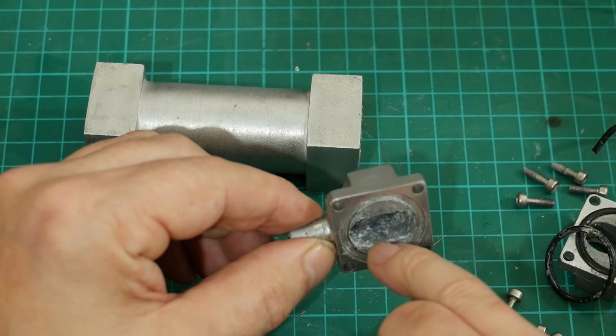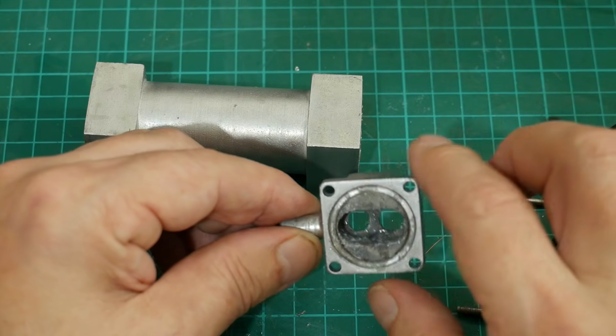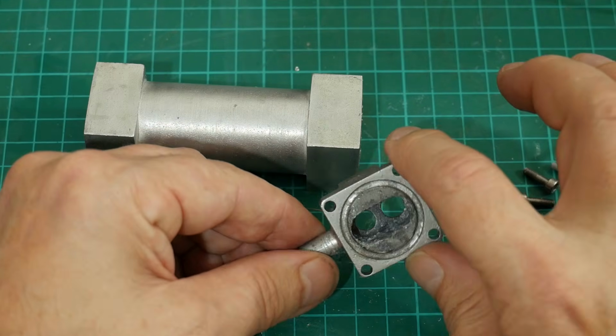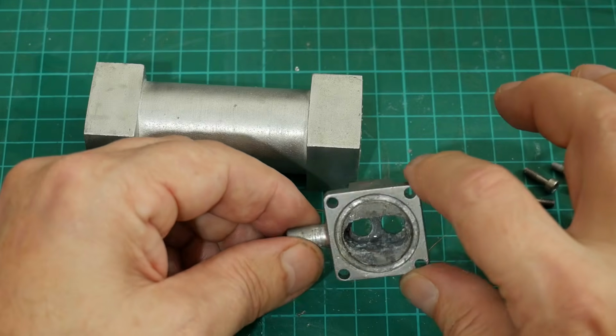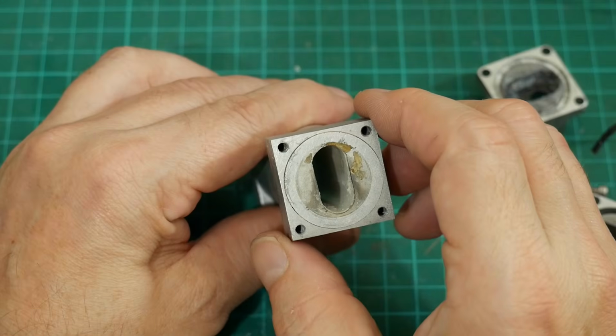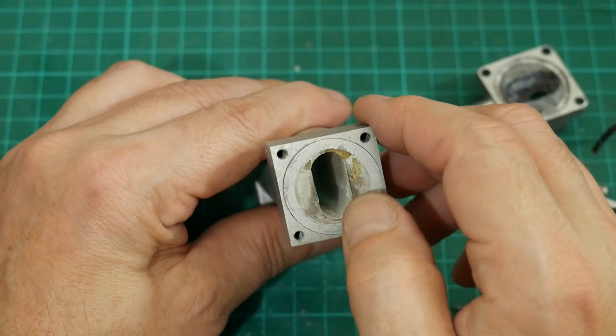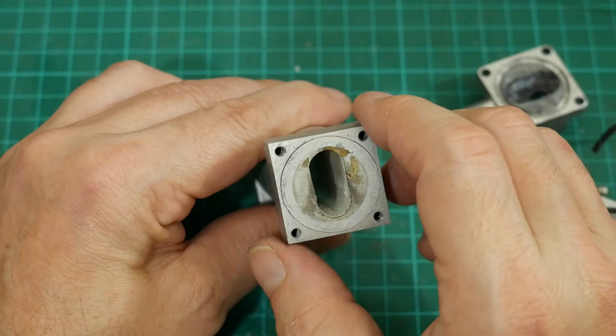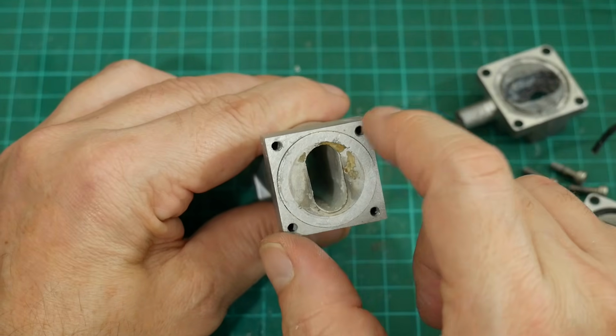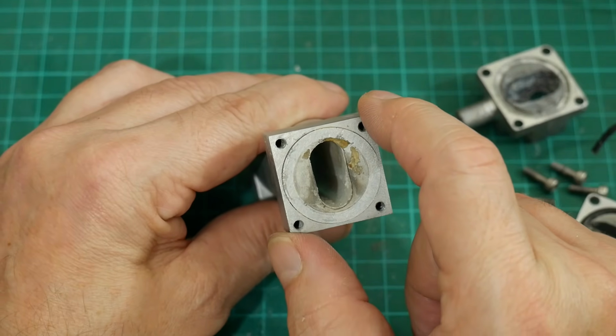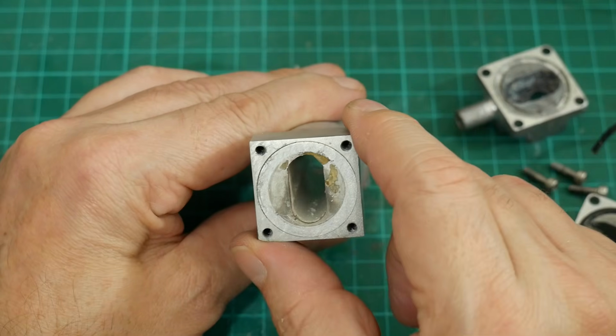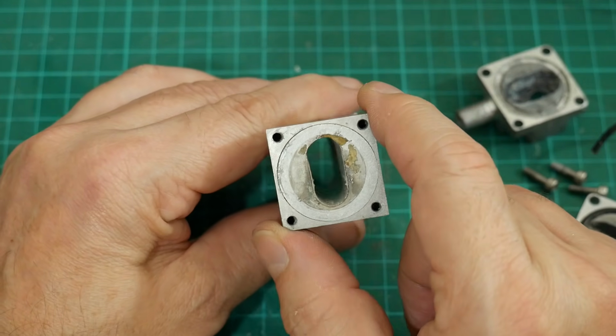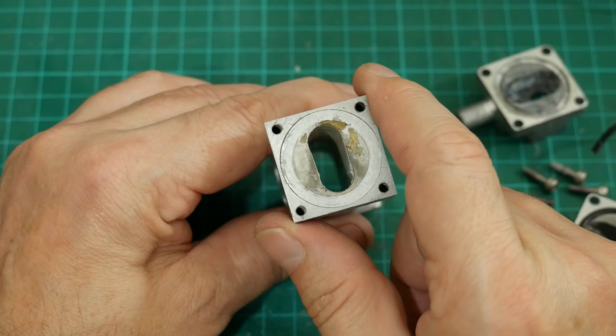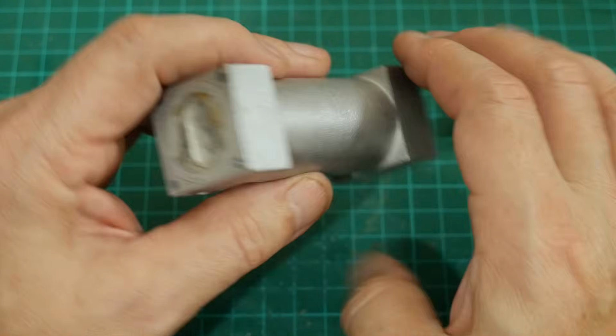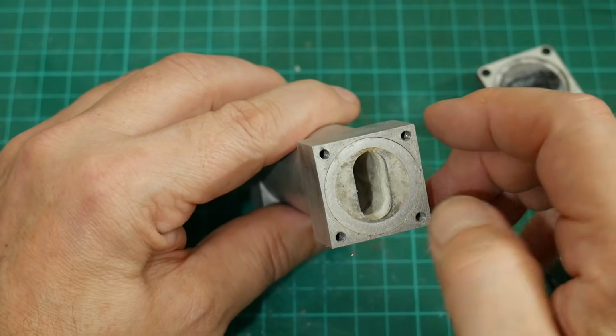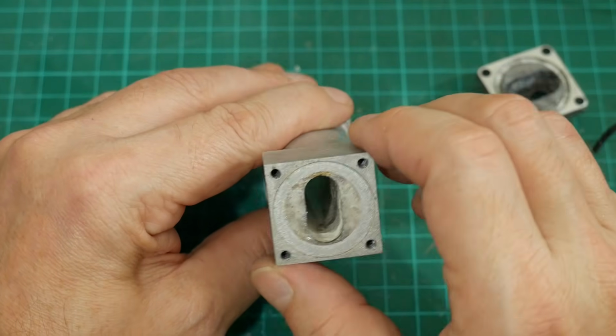I think a little wire brushing with a Dremel attachment will get rid of most of that stuff. But yeah, we can't really expect a laser to work well with this kind of grot floating around in the cavity. This is the inside of the cavity reflector, and this is in particularly poor shape, it has to be said. This is responsible for coupling as much light as possible from the flash lamp into the neodymium YAG rod. If I look down the barrel of this thing, internally there's some scorch marks on the internal surface. It looks kind of blackened. There's some cracks in there. Some of the material's actually starting to erode away at the edges. So this has been really abused.